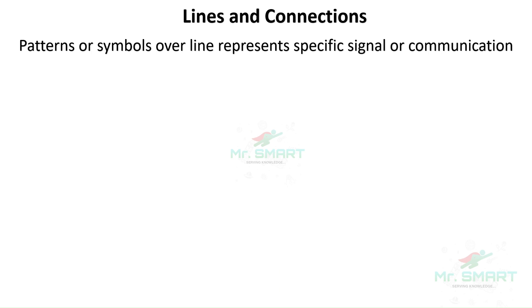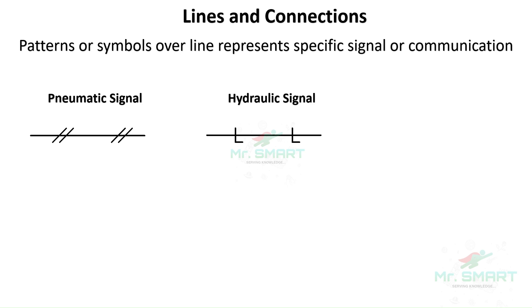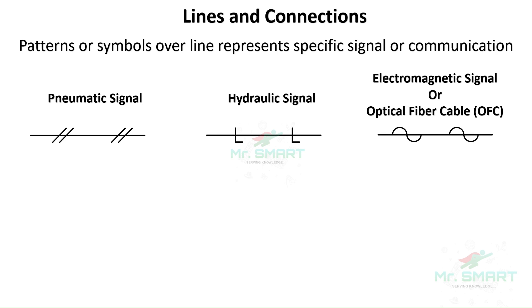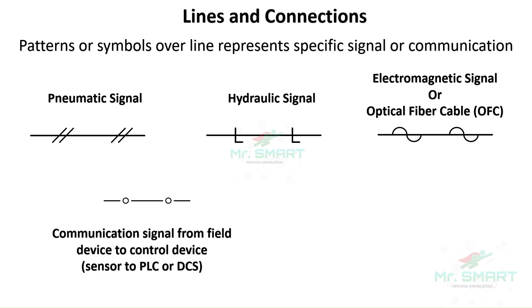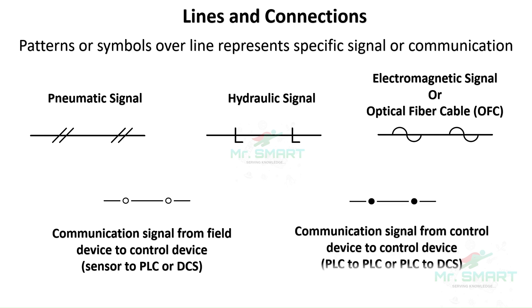Apart from these, some lines have special symbols or patterns over them representing special signal or communication connections. A double-slanted line over the straight line represents the pneumatic actuation signal. An L over the straight line represents the hydraulic actuation signal. A waveform over the straight line represents an electromagnetic signal or optical fiber cable connection. Unfilled or empty circles over the straight line represent communication signals from field devices to control devices. Filled circles over the straight line represent communication signals from control devices to other control devices. These symbols are not common, but knowing them will help you understand the control and communication signal line connections.